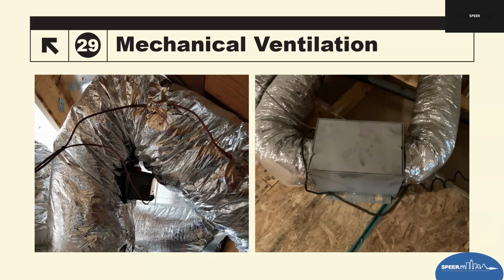So now that the 2021 and beyond requires mechanical ventilation to be tested for proper CFM, if you install ducts like this because you don't think that it matters, you'll have a problem with CFM. And you will have failures where you shouldn't have failures, because the box on the right can do what it's supposed to do by ramping up or down and being set at different settings.